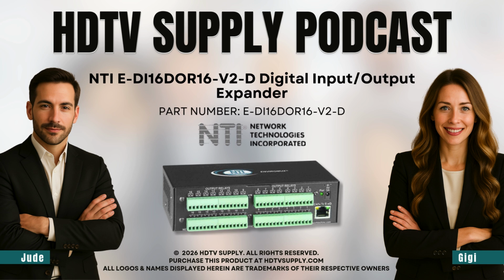So the input side is built for, I'd say, resilience. You get 16 screw terminal pairs for any standard dry contact device. So your basic stuff. Door switches, simple alarms. Exactly. Anything that gives you a simple open or close signal, that's your foundation. In the specs, I saw they're described as potential free. Can you break that down for us? Sure. Potential free just means the inputs themselves don't supply any power. They're passive. They're just listening for a voltage state from whatever you connect. And that makes them super flexible. They can handle 0 to plus 36 VDC, and they're surge protected.